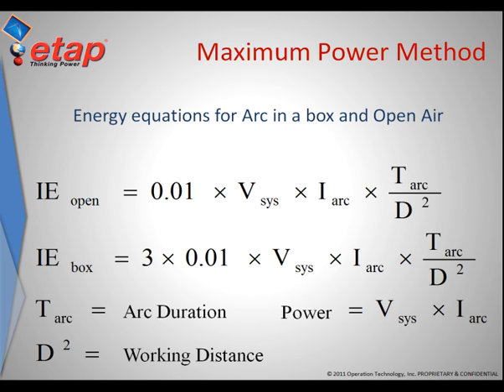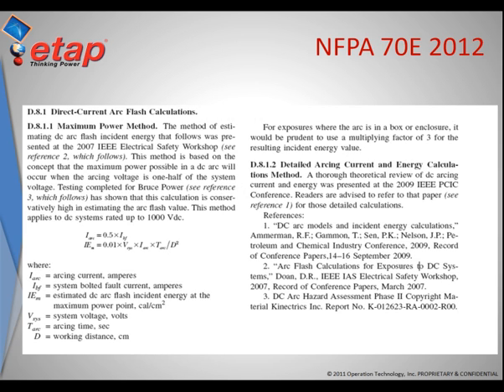The energy equation for an arc in a box or open air is utilized by ETAP to calculate the energy in the system. To calculate the energy of an arc in a box, a factor of three is introduced to account for enclosed equipment. NFPA 70E 2012 talks about this method, and the equations come from this document. Annex D8.1 not only describes these equations but also describes their application and some of the testing done at different sites that validate the model results. This method is considered to yield conservative results for systems rated equal to or less than 1000 volts DC.